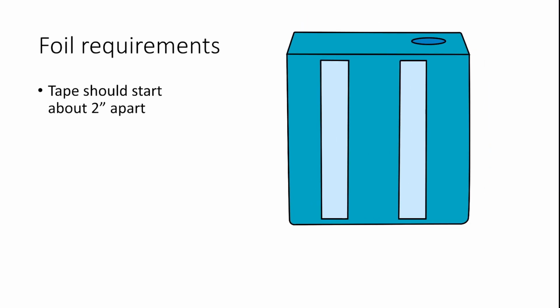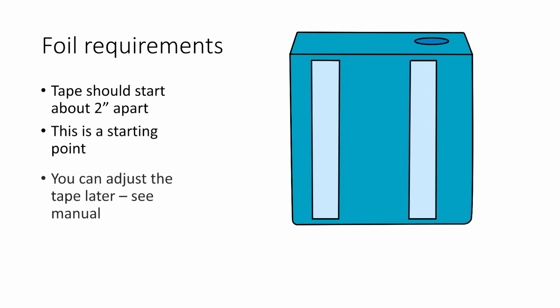Foil requirements. Aluminum tape should start approximately 2 inches apart for the whole height of the tank. This is a starting point but may change after you do your first calibration check. You can do adjustments on the tape if your calibration numbers are not far enough apart for empty and full. See the notes in your manual.